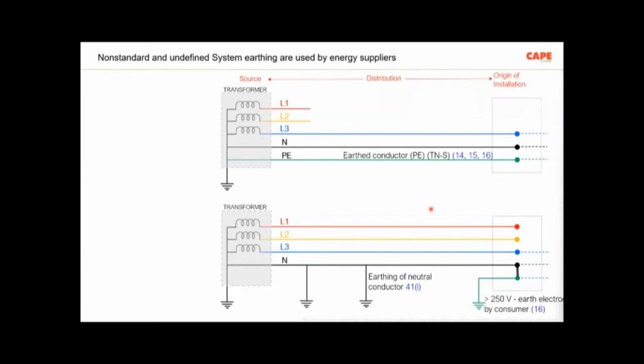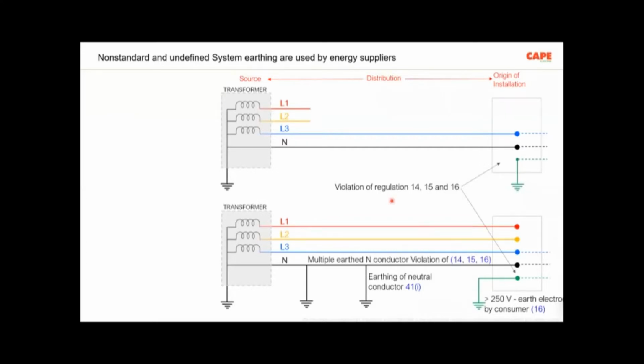But unfortunately, what happens is, one moment, let me hide this. Yeah. Unfortunately, what happens is we are supposed to get the TN-S supply, but our electricity supply company generally doesn't provide this fifth conductor. So they don't provide the link between the earth and the earthed neutral conductor. As a result, the network is actually violating regulations 14, 15, and 16, and the network becomes TT instead of a TN-S system.